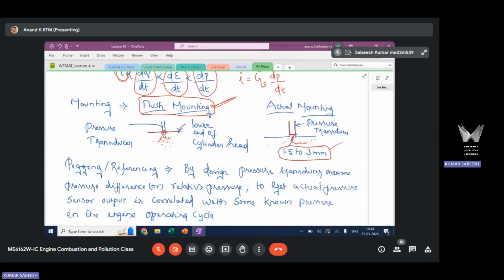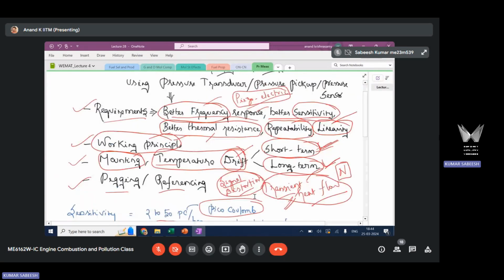Although these problems are there, to avoid the effect of drift, which is the more severe problem, we do this kind of mounting of the pressure sensor. Also, we need to provide sufficient cooling to the sensor.